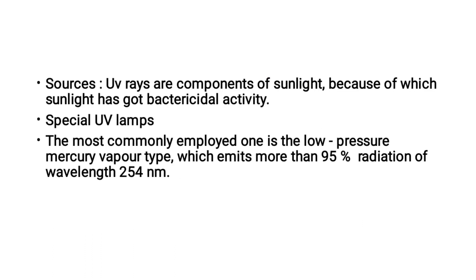The sources of UV rays include sunlight, which is the first natural source and has bactericidal activity. Additionally, special UV lamps are used — the most commonly employed is the low-pressure mercury vapor type lamp, which emits more than 95% radiation at a wavelength of 254 nanometers.